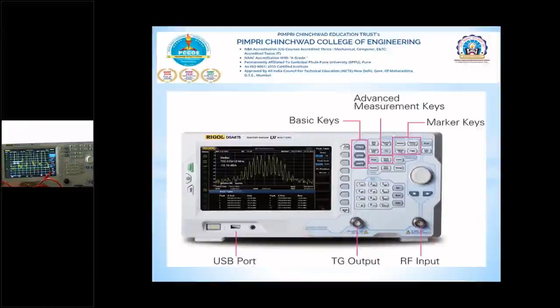For that purpose, there is the AMPT key, among the three basic keys: frequency, span, and below span, AMPT. Once we press AMPT, one window will appear. The first parameter is auto scale. After that, reference level, input attenuation, scaling per division, scale type, and units. The parameter we need here is units. By default the unit is dBm. There are different units to calculate the power. Once we press units, the first unit is dBm, in which we can calculate the power. After that, dB millivolt, dB microvolt, volt, and watts. Generally we analyze the power level in watts, so I will select watt. I have selected watt as the power unit.